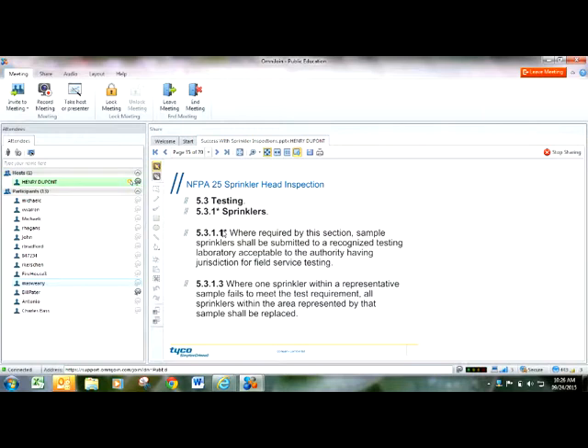Sprinkler head inspections. So say you find a building that has a lot of quick response sprinkler heads that are 25 years old. All right, and I'm the building owner, or I've been cited for this, and I'm going to get these heads tested. This is what NFPA 25 says about getting your sprinkler heads tested. They have to be tested by a recognized laboratory. We like to use Underwriters Laboratory, UL.